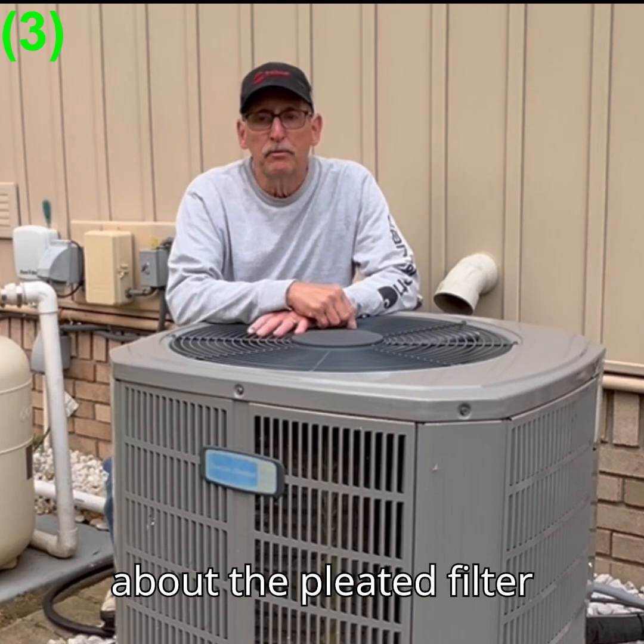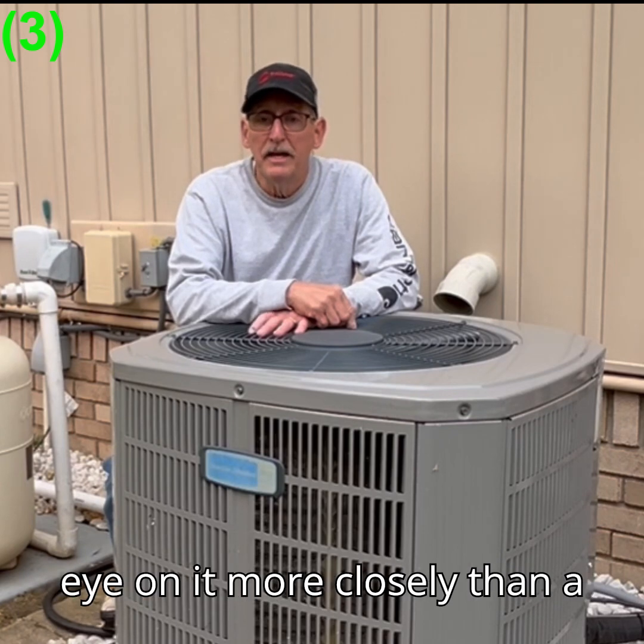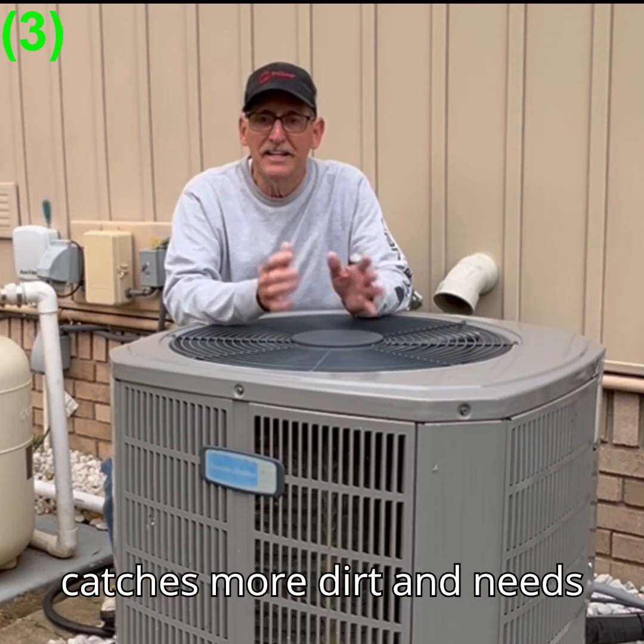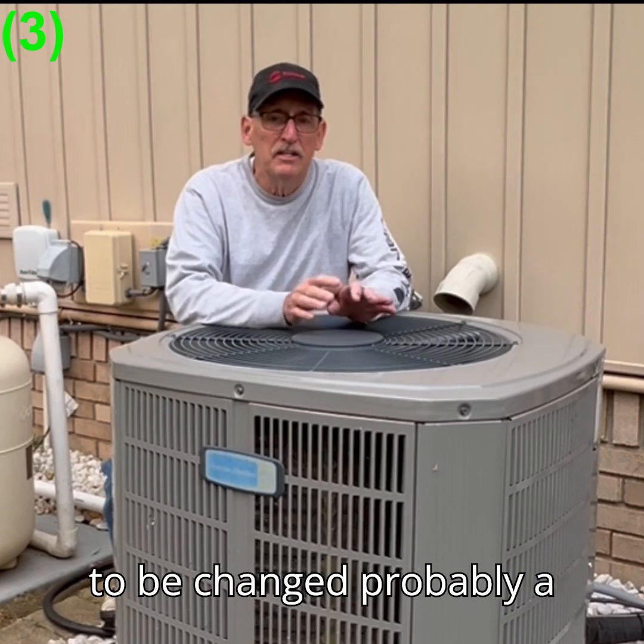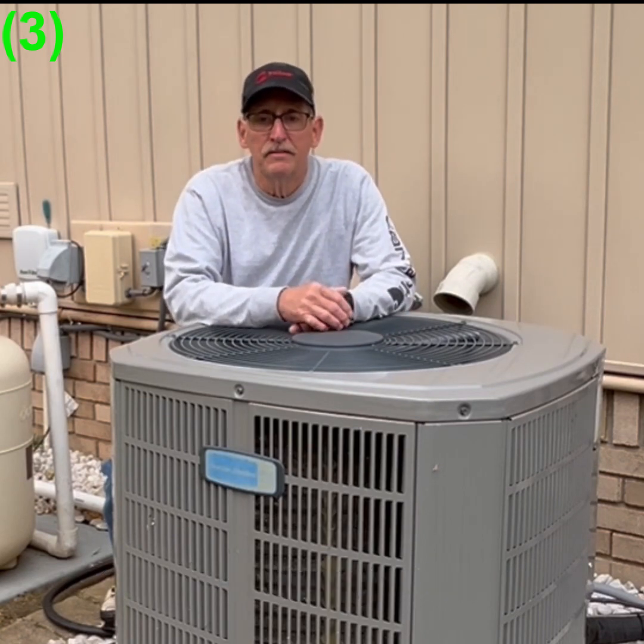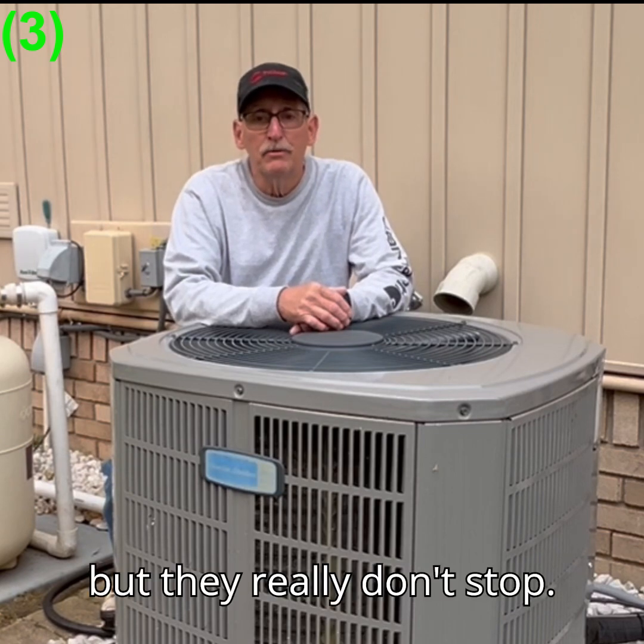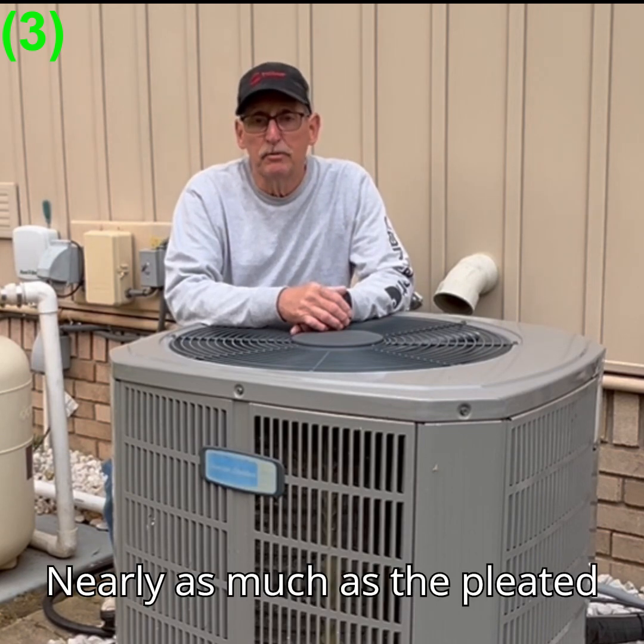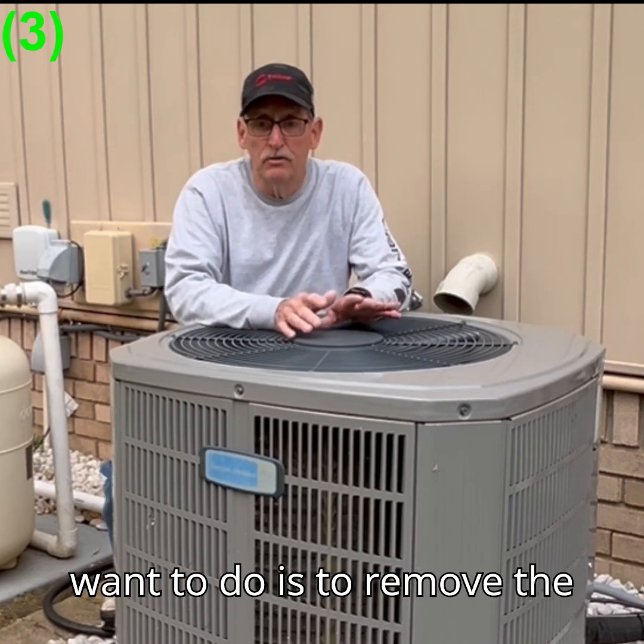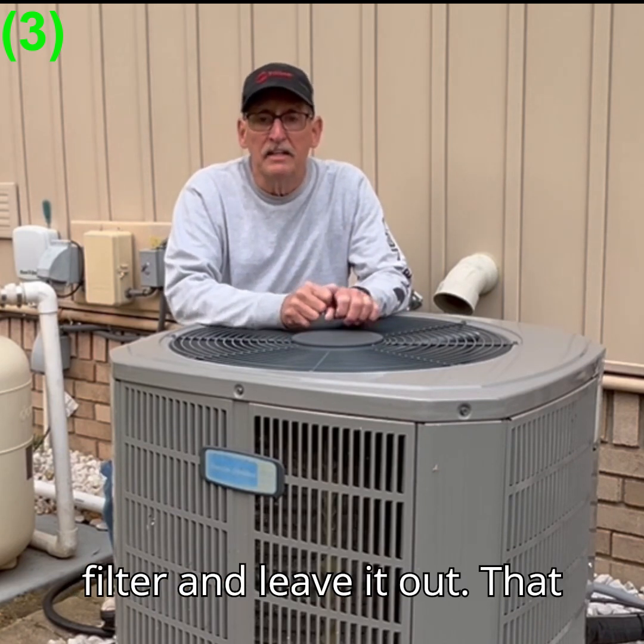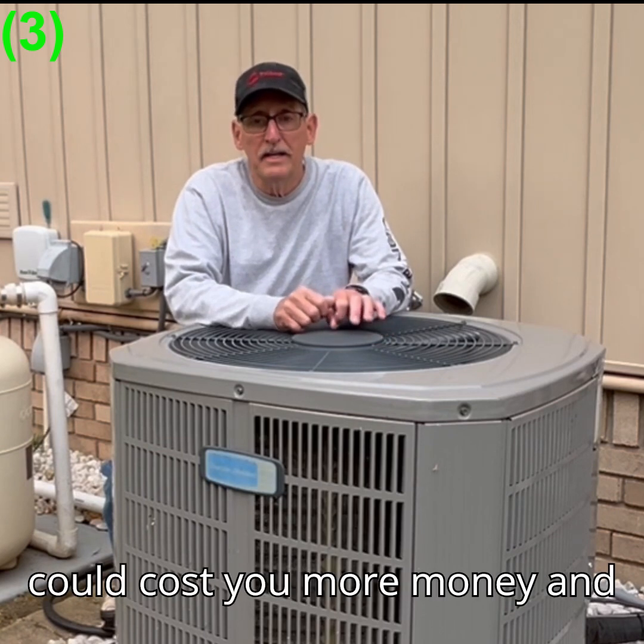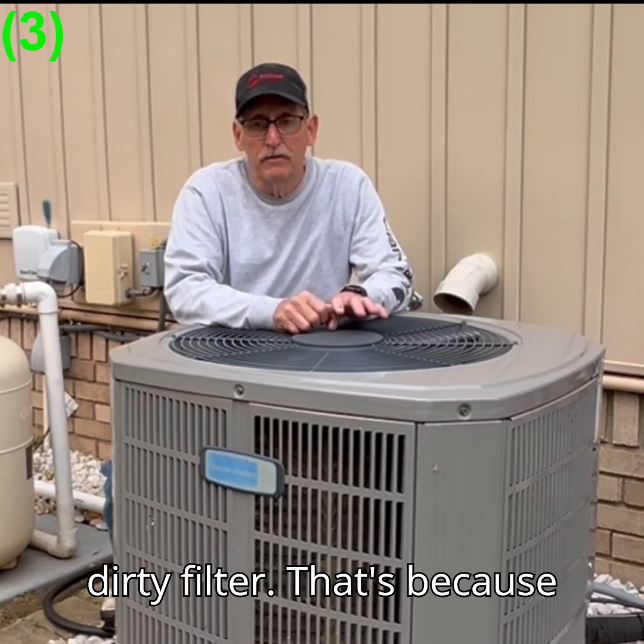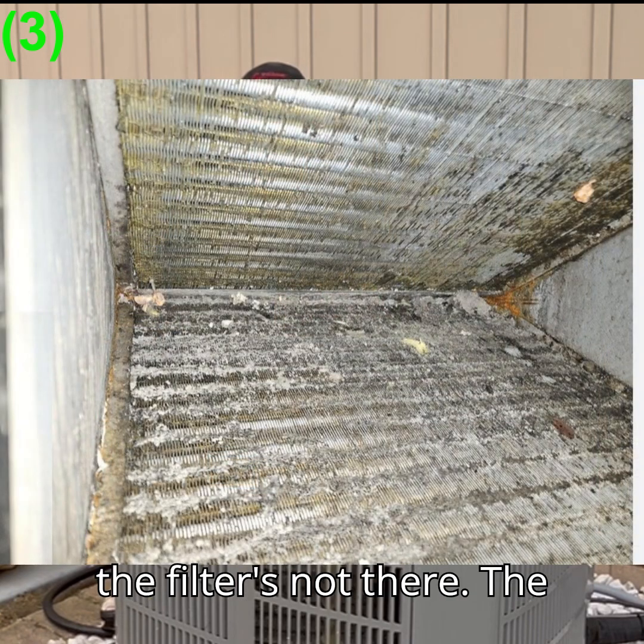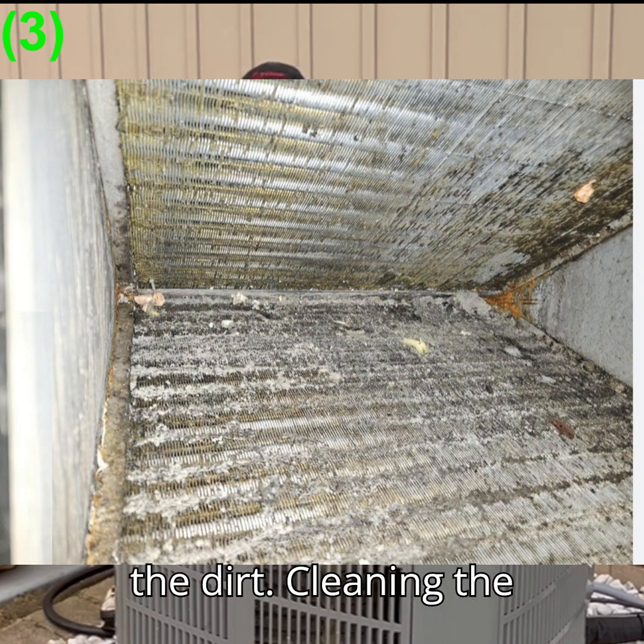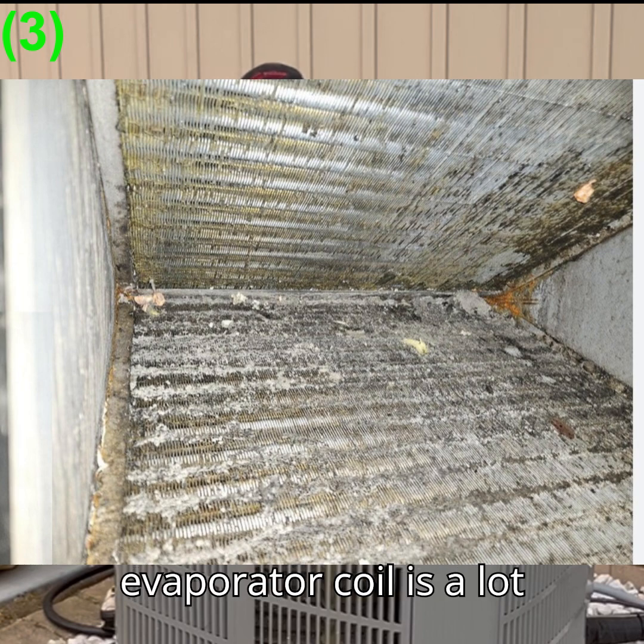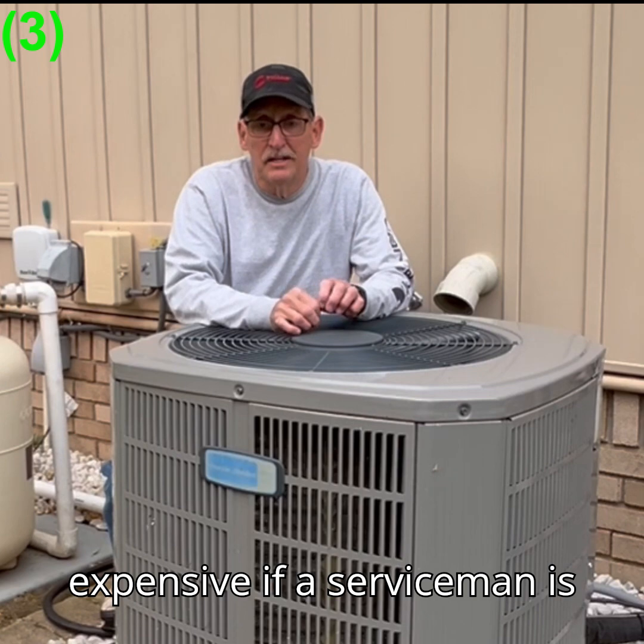One of the things about the pleated filter though is you need to keep an eye on it more closely than a fiberglass filter because it catches more dirt and needs to be changed probably a little bit more often. Fiberglass filters are okay, but they really don't stop nearly as much as the pleated filters. One thing you don't want to do is to remove the filter and leave it out. That could cost you more money and a bigger headache than a dirty filter. That's because if the filter's not there, the evaporator coil will catch the dirt. Cleaning the evaporator coil is a lot harder and a lot more expensive if a serviceman is called.